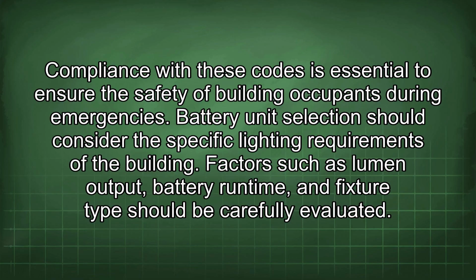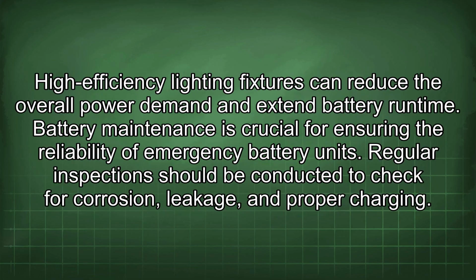Battery unit selection should consider the specific lighting requirements of the building. Factors such as lumen output, battery runtime, and fixture type should be carefully evaluated. High-efficiency lighting fixtures can reduce the overall power demand and extend battery runtime.